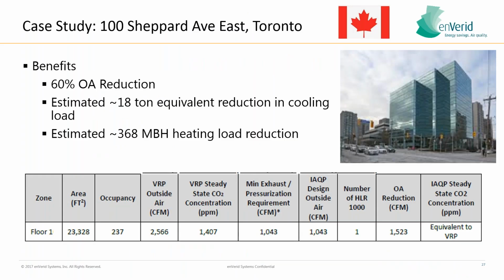Getting a little bit more local, here's a case study at 100 Sheppard Ave East in Toronto. 60% outside air reduction on a single floor, 23,000 square feet, one HLR being used there. 18 ton equivalent reduction in cooling load, 368 MBH of heating load reduction, and the indoor air quality steady state is essentially equivalent to that of ventilation rate procedure, except we're reducing outside air by over 1,500 CFM versus what ventilation rate procedure would have been.